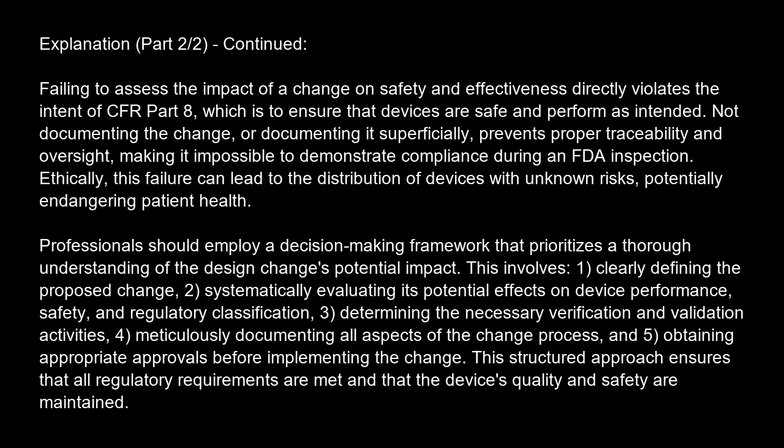2. Systematically evaluating its potential effects on device performance, safety, and regulatory classification. 3. Determining the necessary verification and validation activities. 4. Meticulously documenting all aspects of the change process. And 5. Obtaining appropriate approvals before implementing the change. This structured approach ensures that all regulatory requirements are met and that the device's quality and safety are maintained.